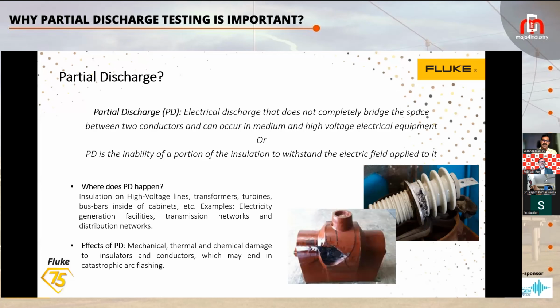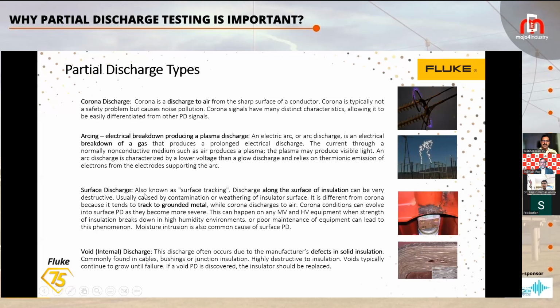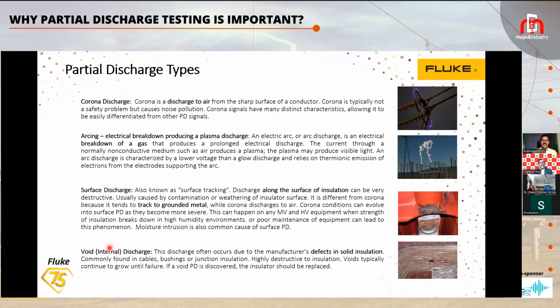When it comes to partial discharge, there are broadly four different categories. One is the corona discharge, the other is arcing, the third is surface discharge, and the fourth is void or internal discharge. Partial discharge is known as corona discharge in many places, and many customers prefer that term. But corona is one portion of partial discharge. Many of you working in high voltage switchgears and transmission lines would have seen such lightning patterns at night or in the evenings. This is actually partial discharge, or the corona effect.